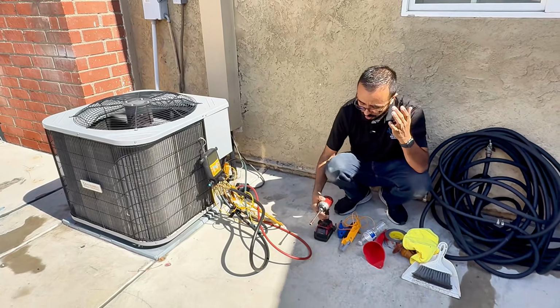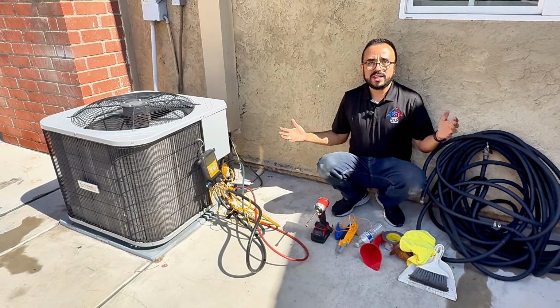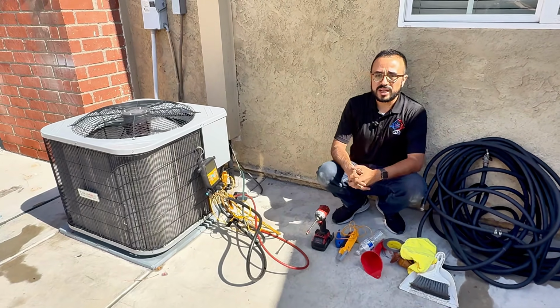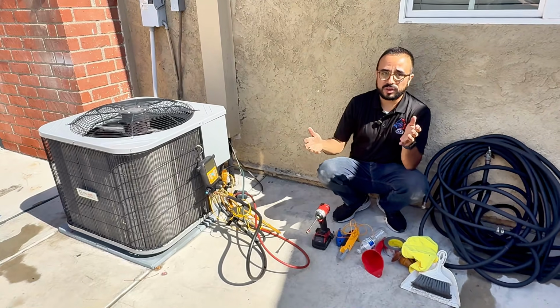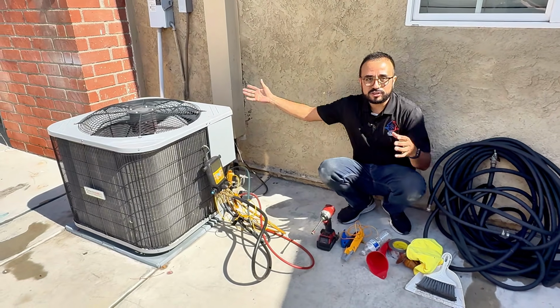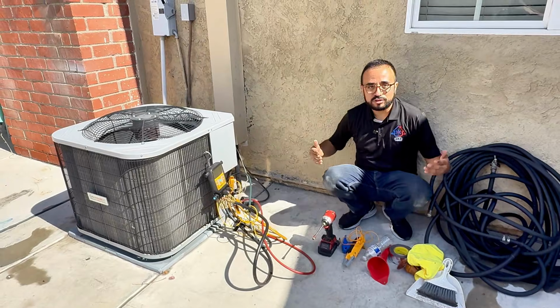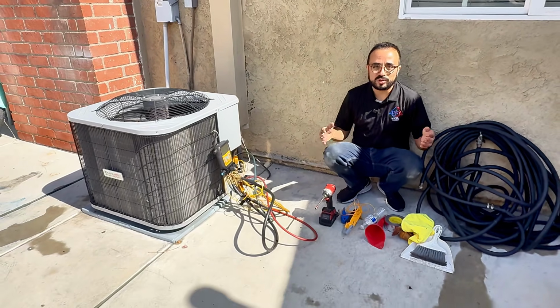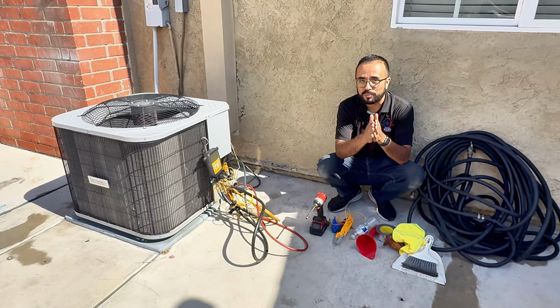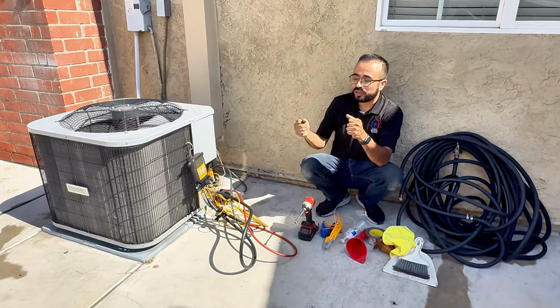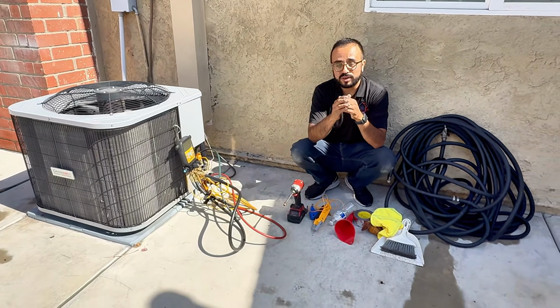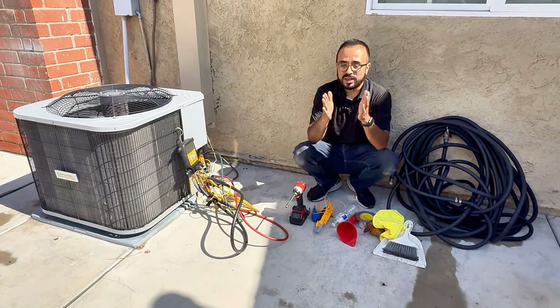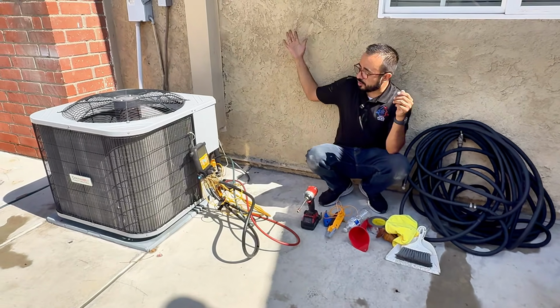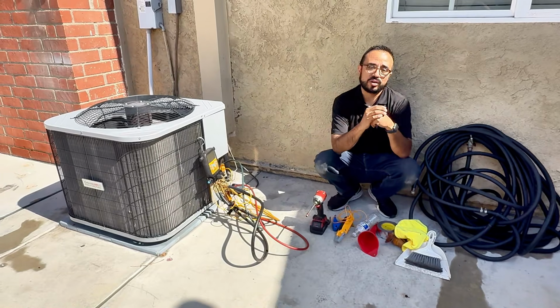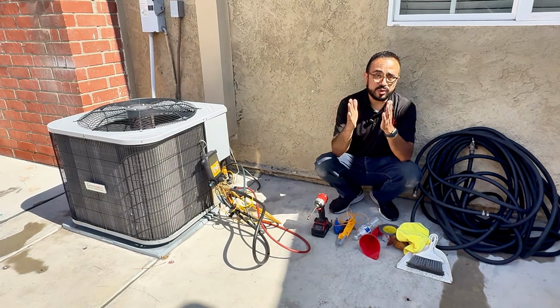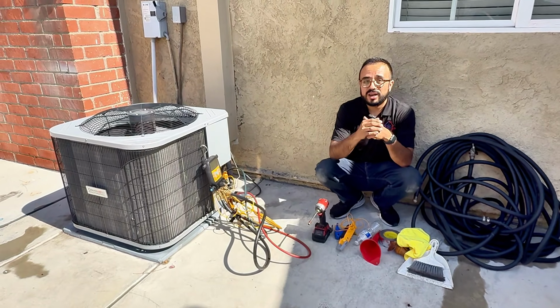So we were to do a full maintenance, and thankfully this system doesn't need really any major repairs, service costs. I'm not gonna go to the customer and say, you need a new unit. It's too old. It's already 7 years old. We don't want to be doing that. We're better than that. So this system is still running strong, and so I'm happy with it. So now I can go and inform the customer that their system's running strong, good delta T, my subcool and superheat are great.